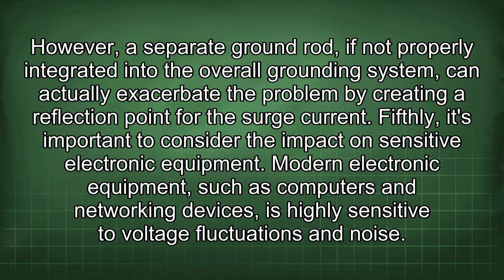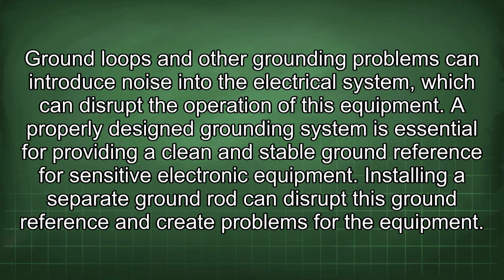Fifthly, it's important to consider the impact on sensitive electronic equipment. Modern electronic equipment, such as computers and networking devices, is highly sensitive to voltage fluctuations and noise. Ground loops and other grounding problems can introduce noise into the electrical system, which can disrupt the operation of this equipment. A properly designed grounding system is essential for providing a clean and stable ground reference for sensitive electronic equipment. Installing a separate ground rod can disrupt this ground reference and create problems for the equipment.